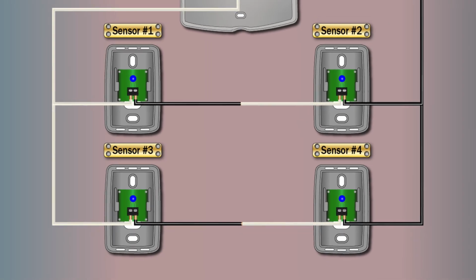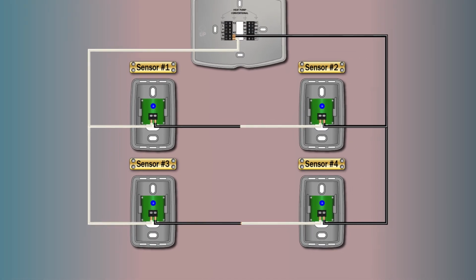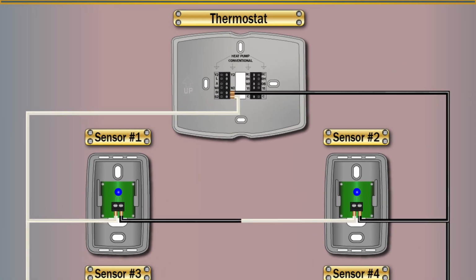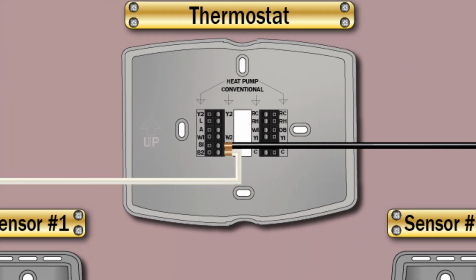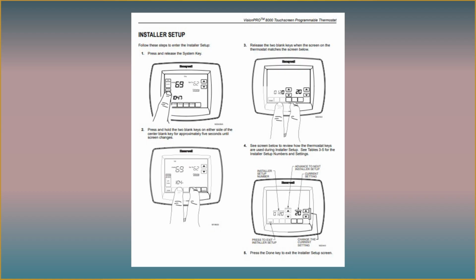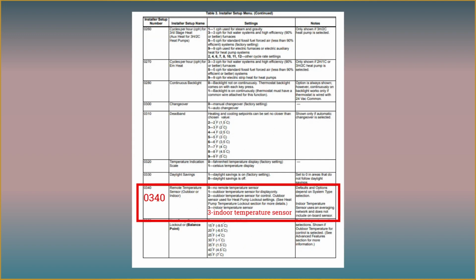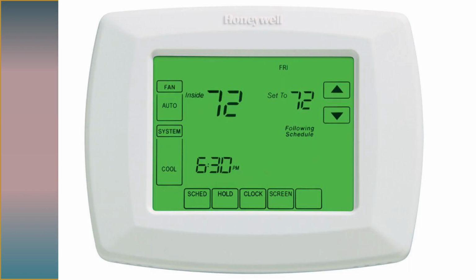Next, terminate the 4 sensors in the space and land the 2 wires on the thermostat remote sensor terminal on the subbase as indicated in the diagram. Then go into the installer menu of the thermostat, enable the remote temperature sensor function, selecting the 10K ohm thermistor setting. Now the temperature displayed on the front of the thermostat should reflect the average temperature of the space for the 4 zones.